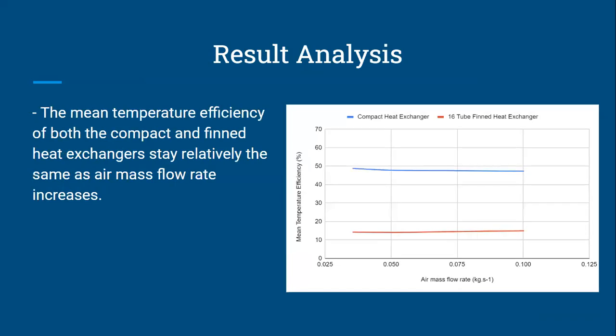In this graph, we are now comparing the mean temperature efficiency to air mass flow rate. We can see that the compact heat exchanger with the increased surface area is much more efficient at transferring heat than the finned heat exchanger that has less surface area, with both heat exchangers' temperature efficiency staying fairly constant as the air mass flow rate increases.